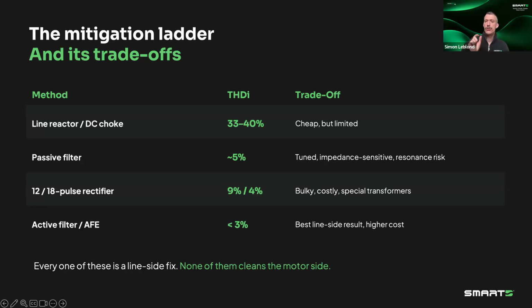Passive filters are tuned to a specific impedance and at specific loads. So as loads come on and off, system impedance can change, and the resonant frequency calibrated for the full load can actually become a resonant amplifier at partial load. So you're potentially worsening the distortion at certain frequencies rather than suppressing them. And I've actually seen this in some hospital settings, as you see some suites coming on and off throughout the day. That's also a phenomenon you're seeing in data centers, where your IT load will shift over the course of the day, but also over the course of the week. So think of a passive filter as a snapshot solution that's really trying to address a moving target.